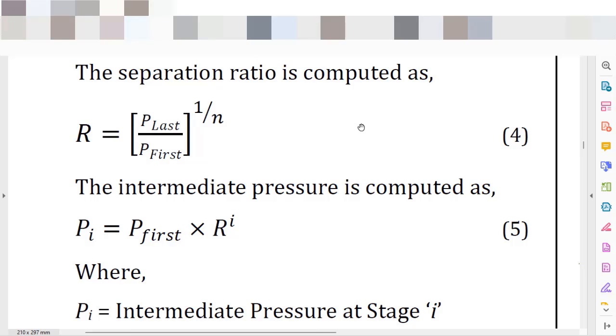Here I will differentiate two pressure ratios. The first one is the global pressure ratio, calculated based on the discharge pressure of your final stage. So if you have five stages of compression, you take the discharge pressure of stage 5 and divide it by the inlet pressure of stage 1 — the inlet condition divided into the discharge condition. Both pressures must be in absolute pressure: PSI A with PSI A, or bar A with bar A.